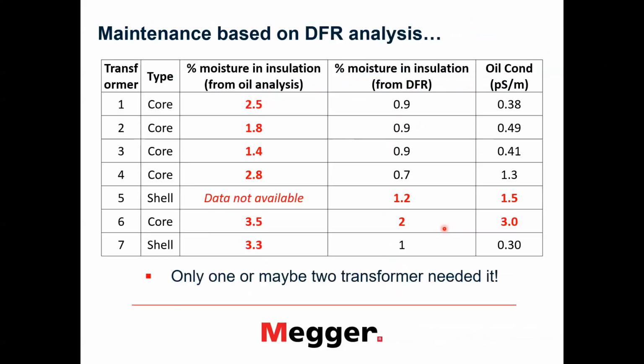And when doing the frequency response measurements on these transformers and making the modeling from IDAX software, it appears that only one transformer may need to be subjected to some overhaul or maintenance. The rest of them were pretty much all right. So this is just again an illustration that direct methods on oil samples may not give you a correct answer. You have to be aware of it, simply as that.